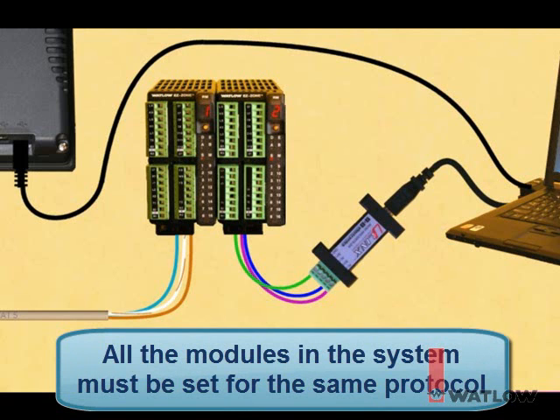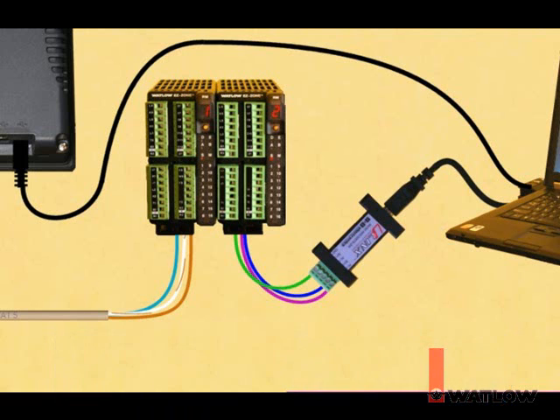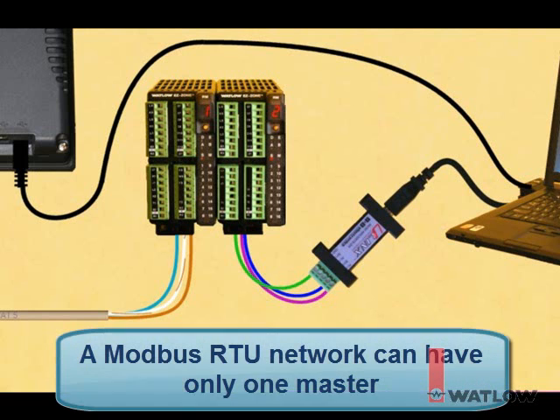We'll start with all the modules set to standard bus so that we can configure them with EZ-ZONE Configurator software. While we do that, we'll leave the OIT powered off. Later, we'll switch the RM modules to Modbus RTU so they can communicate with the OIT, and we won't run EZ-ZONE Configurator on the PC. Finally, a Modbus RTU network can have only one master, so at any one time the OIT can communicate with the RM controllers, or EasyWare 5000's online simulator can, but not both at the same time.